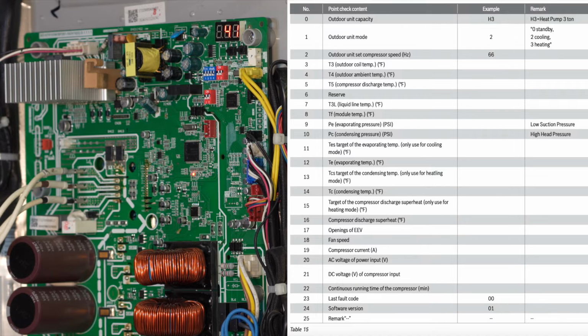Number 3 is your T3 outdoor coil sensor. It was showing 89. Now keep in mind, we're in a building here, so some of these temperatures will be a little different than they would actually be in the field. Number 4 is a T4 outdoor ambient sensor. That's our little ambient sensor that hangs down out of the bottom of our control panel here, giving us outdoor temperature. 5 was compressor discharge temperature. At that time, once again, in the forced mode, we were at 127. Number 6 was double dashes or triple dashes. And on the 15 and 18, that's shown as a reserve. On the 20 SEER, it has an extra sensor that the 15 and the 18 don't have. So if you flip over to the 20 SEER parameters and look at number 6, you're going to see that that extra sensor is a TH compressor suction temperature thermistor that the 15 and the 18 don't have.